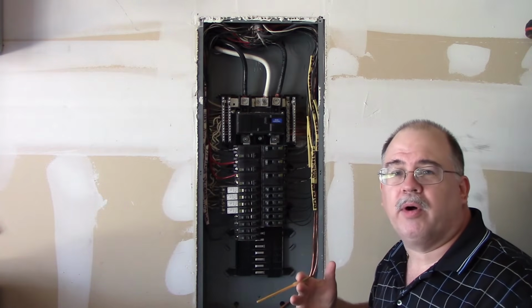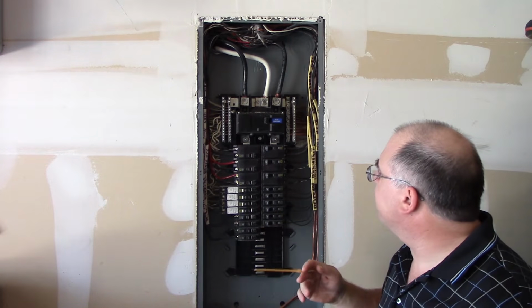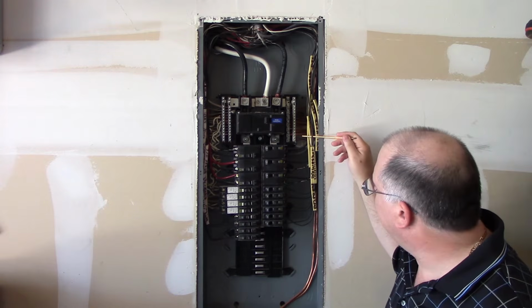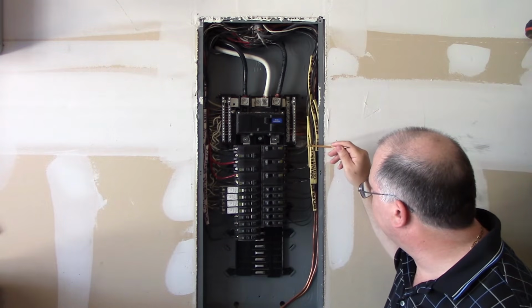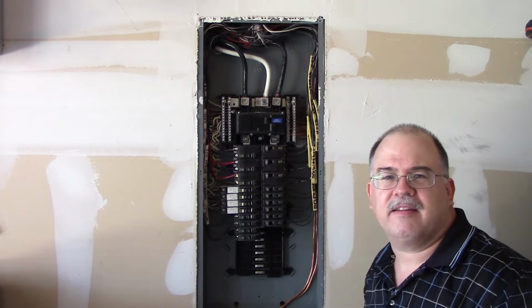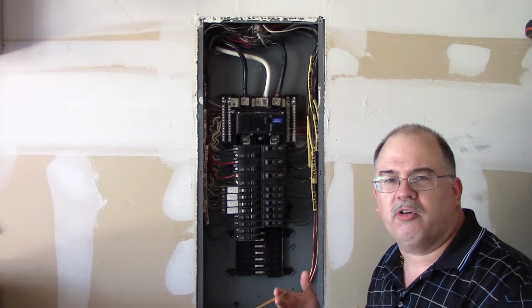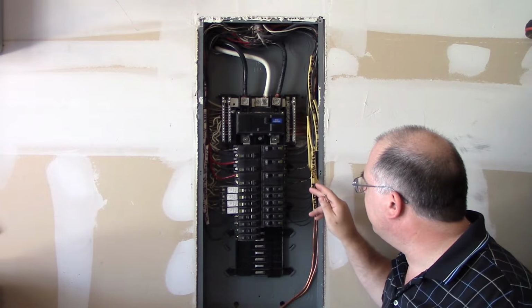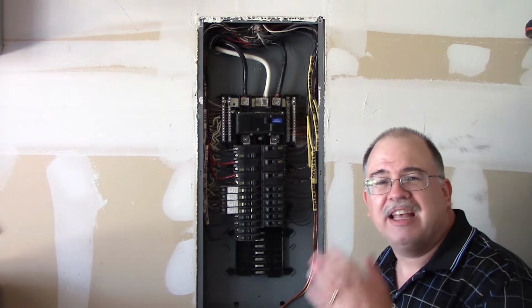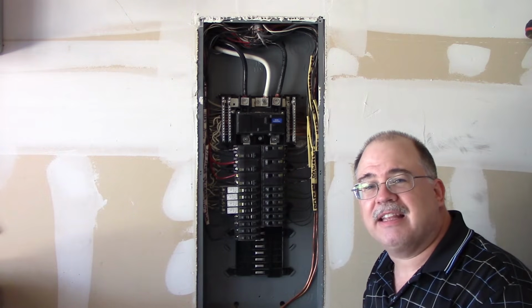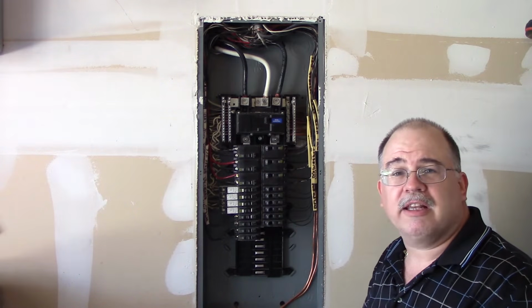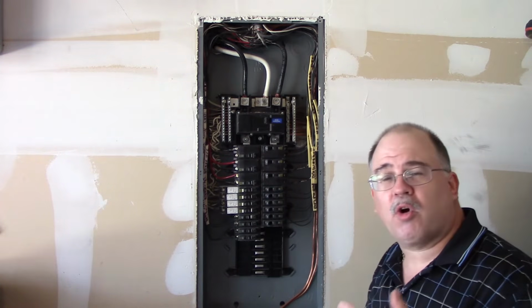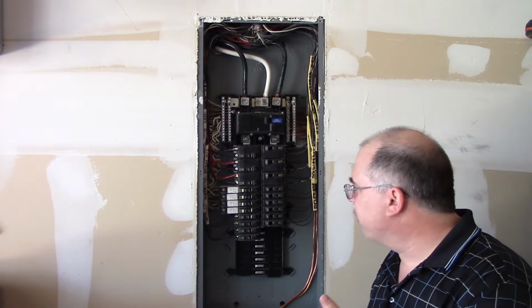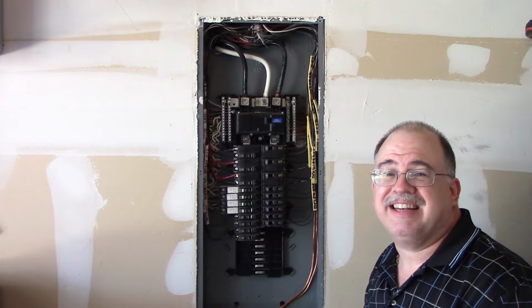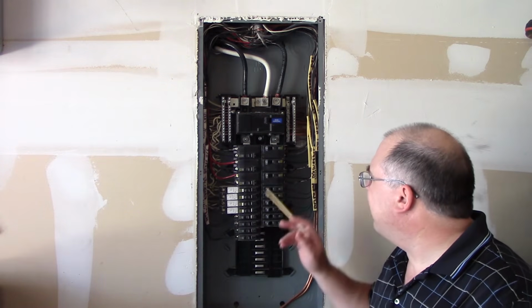But we wanted to point out some things in here. This is non-metallic sheath cable, and actually they left the actual sheeting on here. Some people have a concern with that because they say it's combustible material within the enclosure. I have no problem with it because I know that there's fire retardant properties inside of this non-metallic sheath cable because it is installed in a dwelling, and that is a requirement of the standard for non-metallic sheath cable, which is UL 719. So I don't have a problem with that.